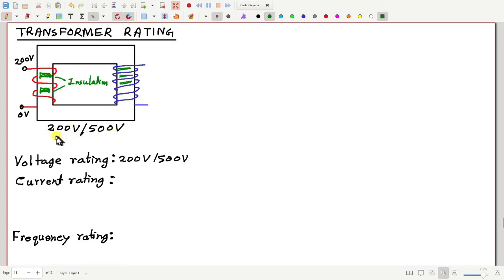But if this transformer is designed for 200 volt by 500 volt operation, then if you work with higher voltage, these insulations, the inter-turn insulation, and also the insulation between the coil and the core, may not be able to withstand the higher level of voltages. There may be a spark or flashover through the insulation, which may damage the transformer, which may cause dangerous accidents. So we should not operate beyond the specified or rated voltage for a transformer.